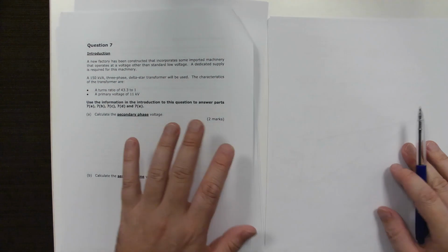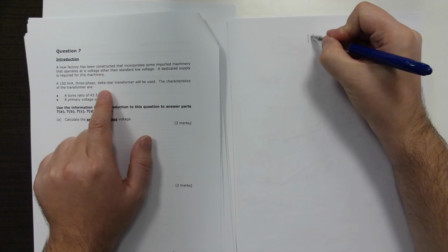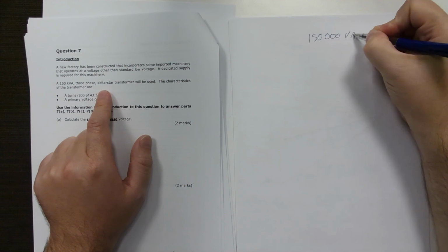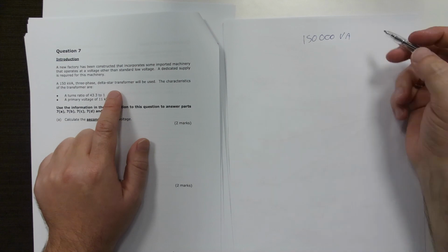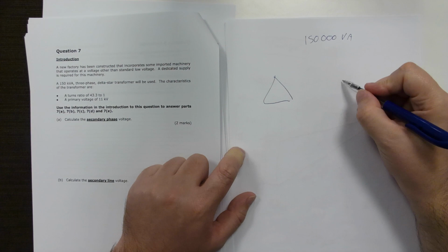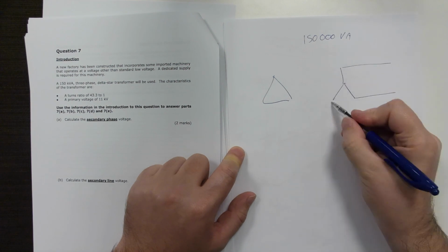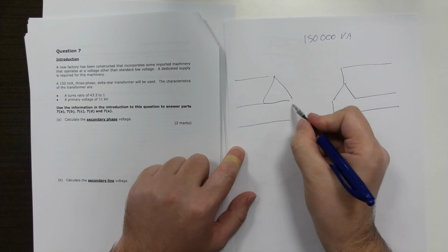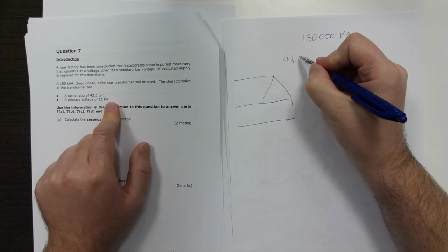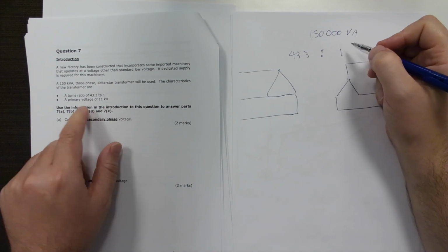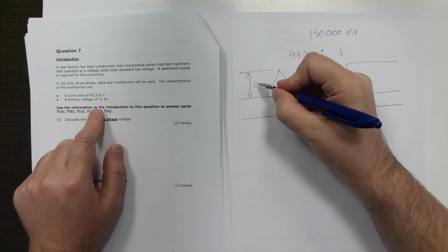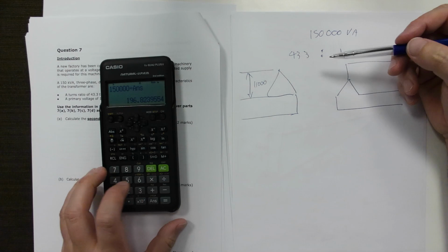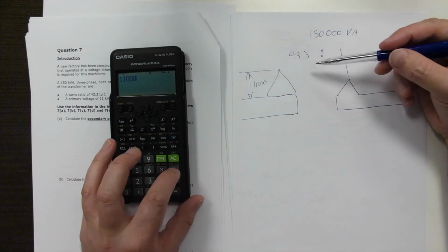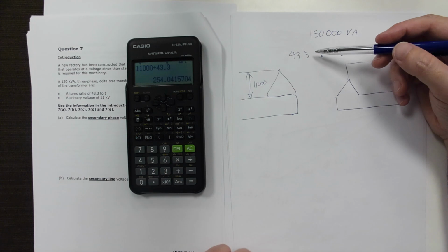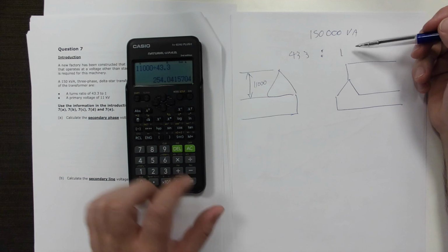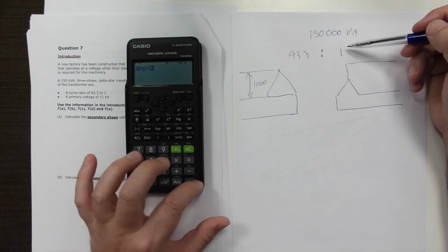So let's start by drawing this. It is a 150 kVA. Write out the full value, so 150,000 VA. It is delta star, so we draw our delta and we draw our star. Now we know it is 43.3 to 1, and we know the primary is 11,000. Now we get our primary and we divide it by our 43.3. Because it's 1 on this side, we don't have to multiply it by anything. If it was 2, we would multiply it by 2. In this case, it's multiplied by 1, so it's the same value.